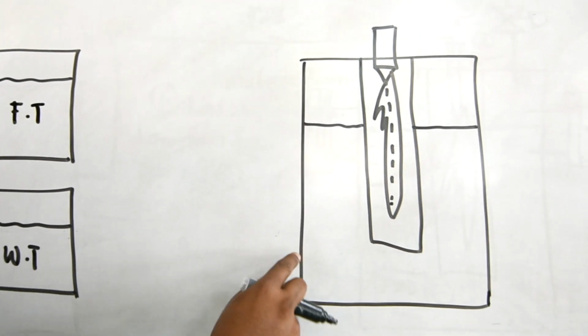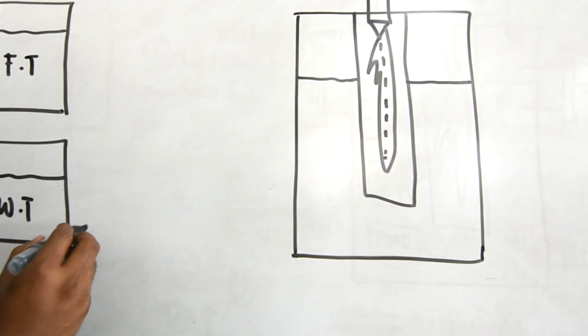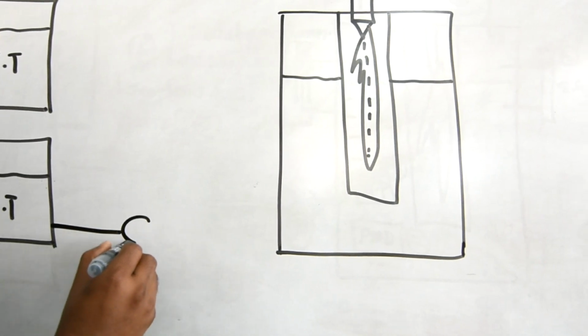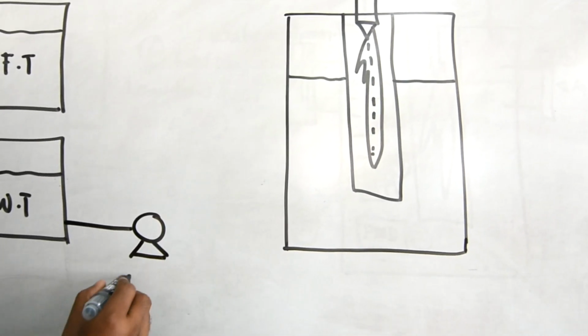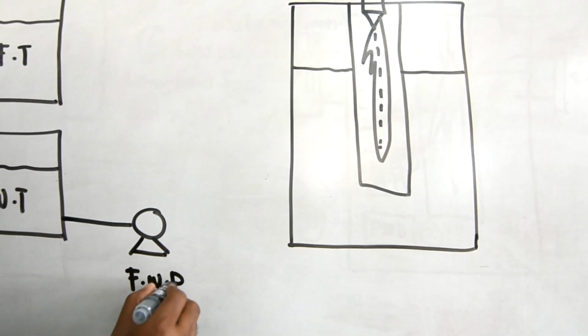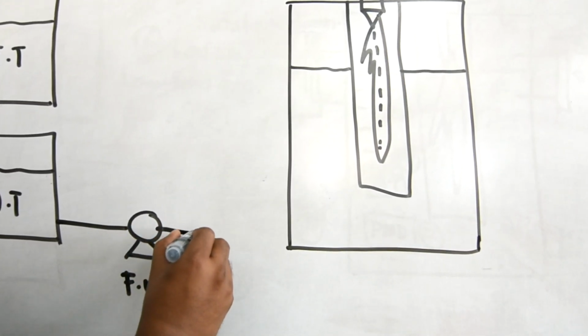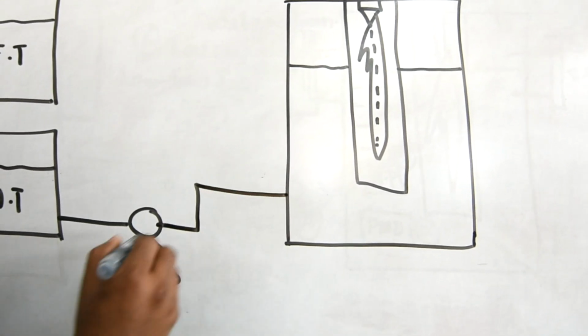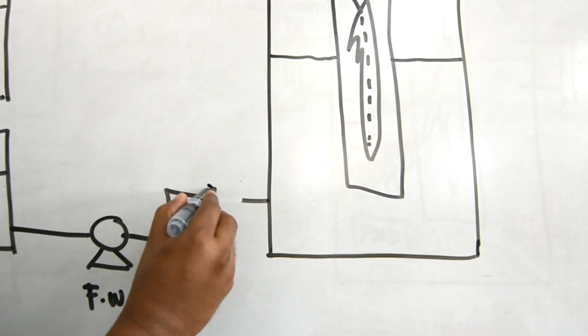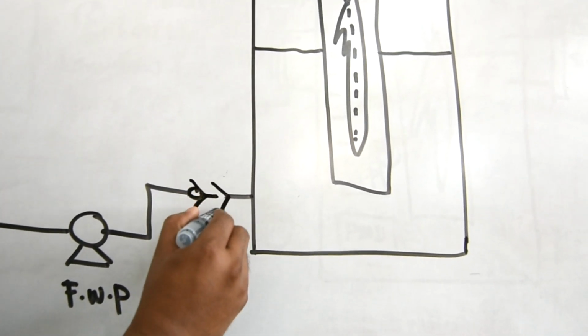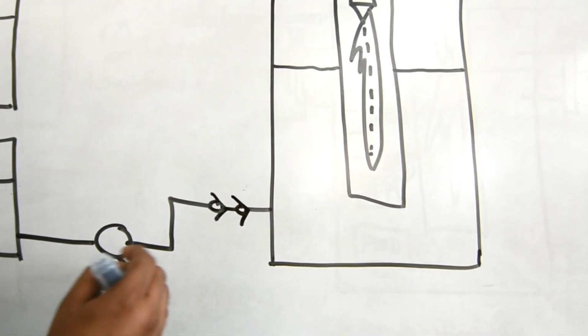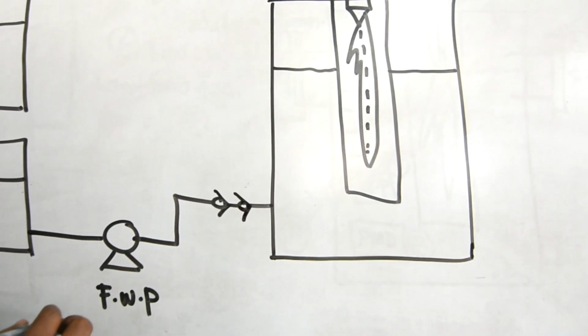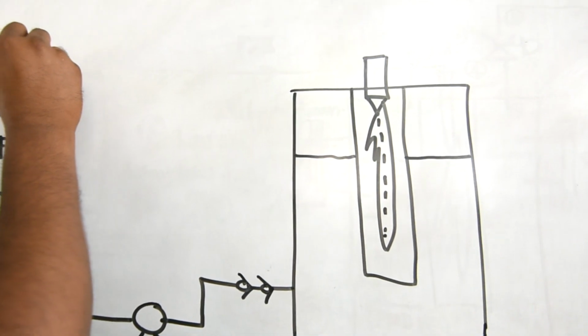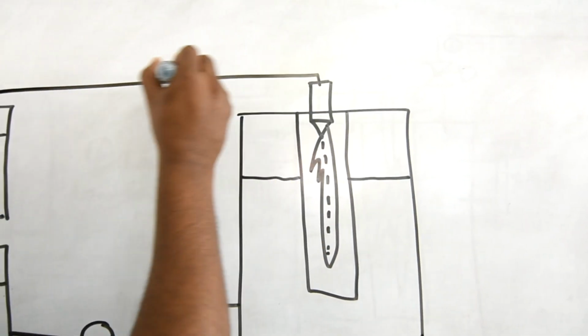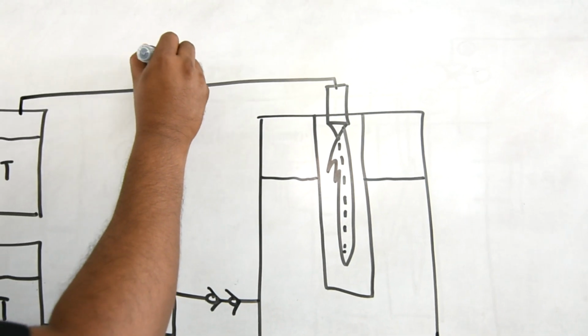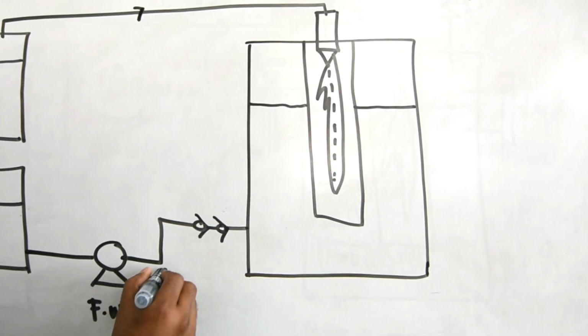Okay. Now for the boiler, the most important thing is that it needs to be fed with water. Water supply. So it comes with the feed water pump. So this is the feed water pump. This feed water pump will pump into the boiler. And in between this, there's a check valve. This is the check valve over here, in order to avoid back pressure from the boiler. Then here we will have a fuel supply line for the burner. So this is the fuel supply and this is your water supply.